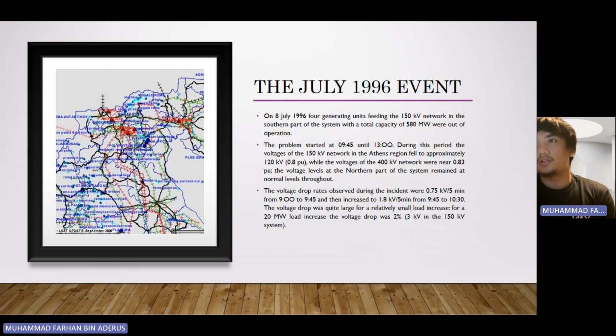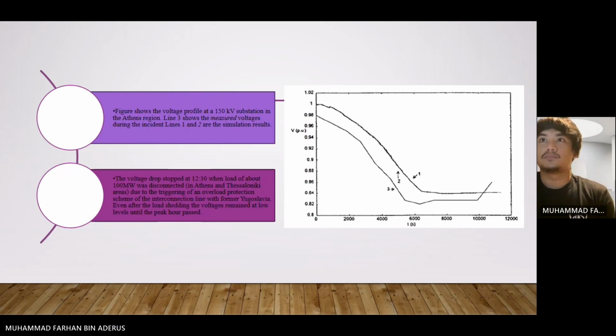The voltage drop was quite large for a relatively small load increase. For a 20 megawatt load increase, the voltage drop was 2%, which is 3 kilovolt in the 150 kilovolt total. The figures show the line voltage at a 150 kV substation in the Athens region. Line 3 shows the measured voltage during the incident, and line 1 and line 2 are simulation results.